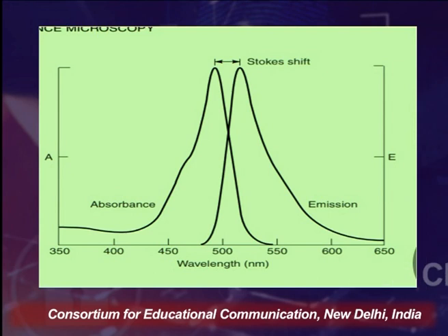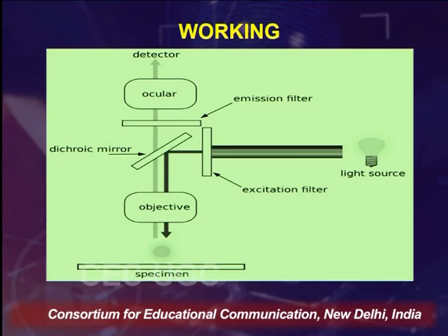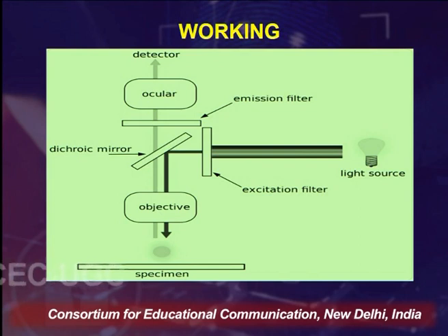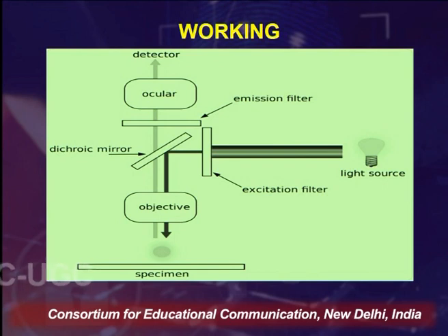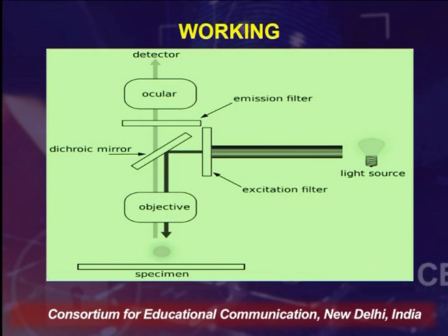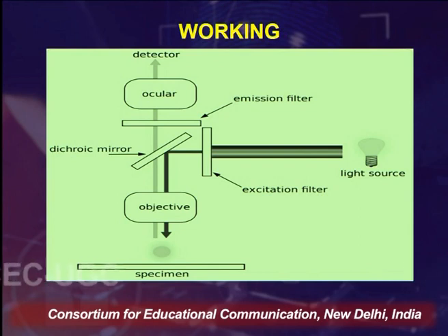Talking about the working of the fluorescence microscope: there is a light source through which light passes through the excitation filter. From the excitation filter the light goes through the dichroic mirror to the objective and from there to the specimen. The specimen, after receiving the light, goes to the excited state, and when it returns to the ground state it emits some light. That emitted light contains fluorescent light, which goes back through the dichroic mirror, then to the ocular and detector. The detector detects that fluorescent light, and its absorption spectra helps identify the substance being examined.